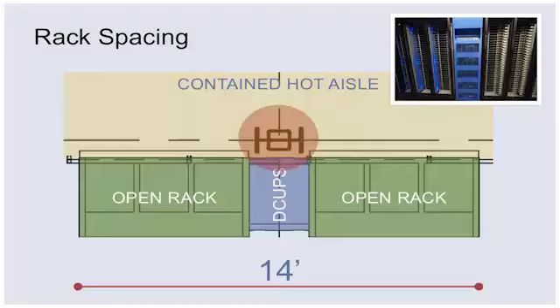Because we wanted a clear data hall space with limited obstructions and no columns in the way of our overhead distribution, we located our columns in the hot aisle containment section of our data hall. All our technicians would only have to service the server from the cold aisle, so power and data would drop on that cold aisle side.